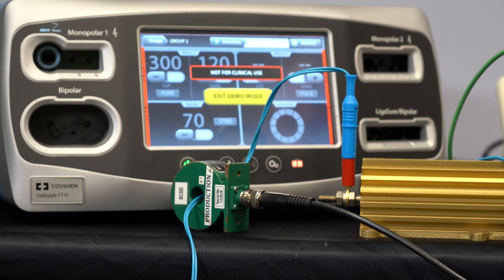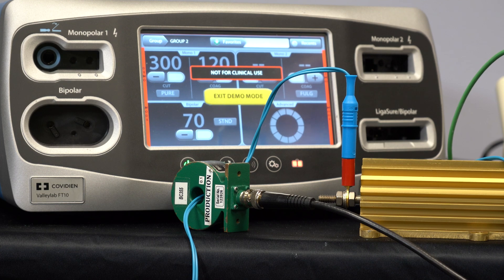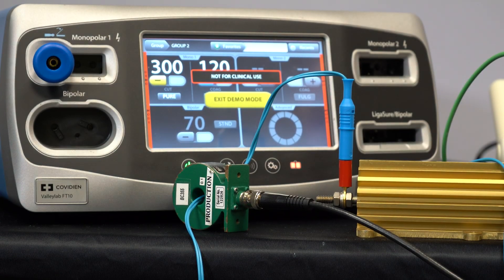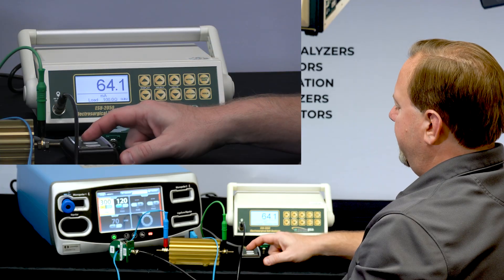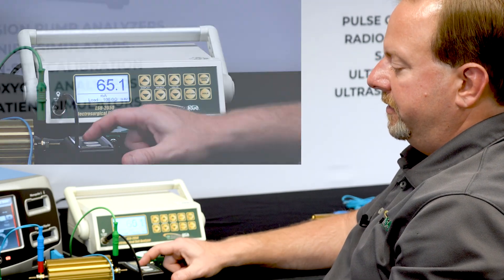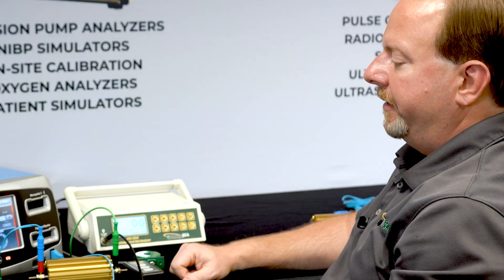Now it doesn't think there's anything plugged into my monopolar one port so it won't let me activate the generator. I'll plug in the adapter. It will allow me to activate the generator and we can take our measurement and determine whether that's within the limits for cut and coag at maximum power. Thank you for watching.